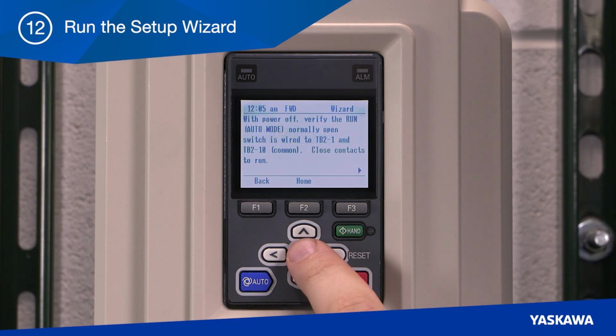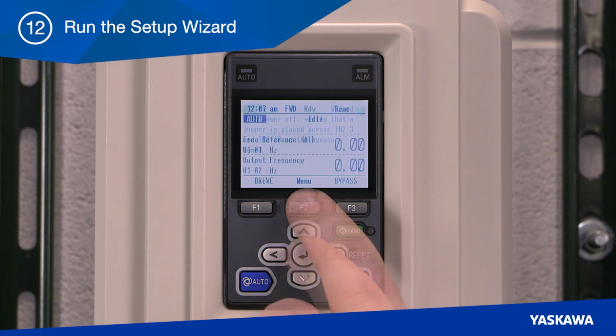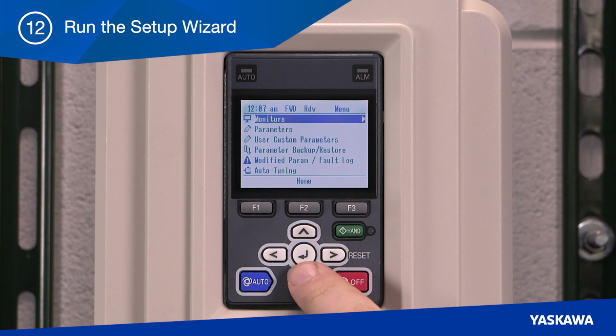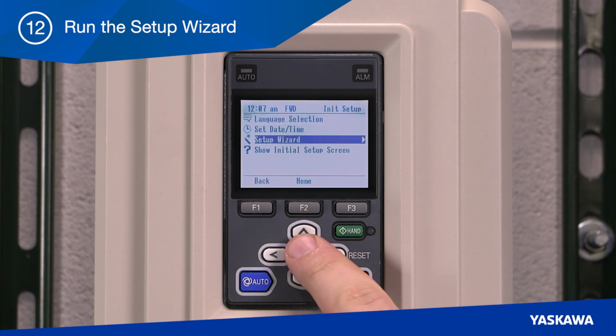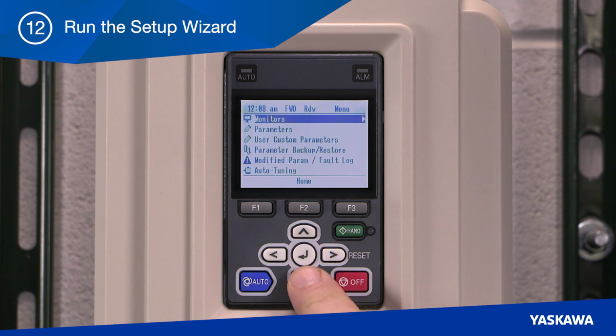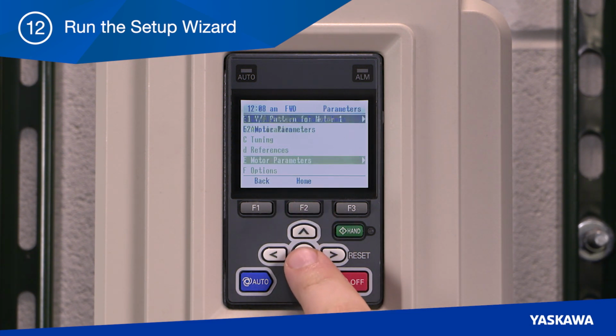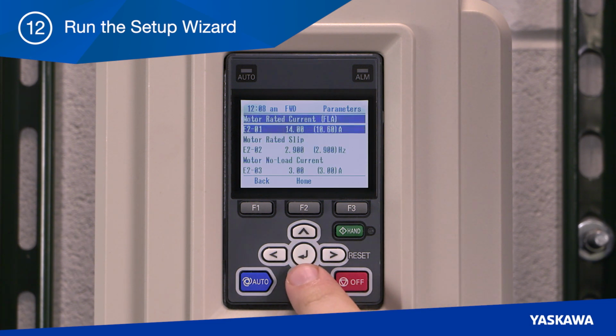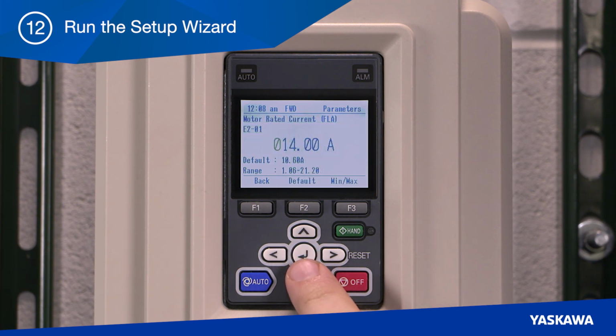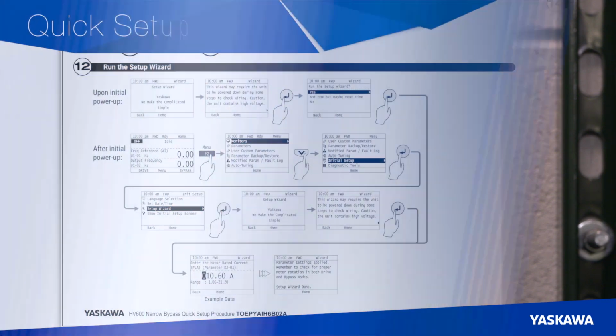As you navigate through the wizard, notice all the helpful pointers shown to help make bypass startup easy. Note, if you are not automatically prompted with the wizard, navigate to the initial setup menu and select the Setup Wizard. You can also directly set the motor-rated current parameter E201 without the Setup Wizard if you are already familiar with the programming of Yaskawa AC drive products.